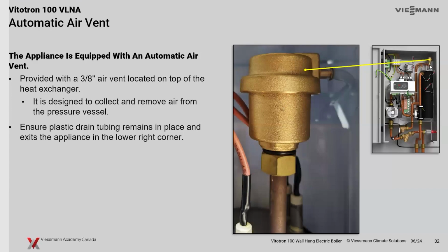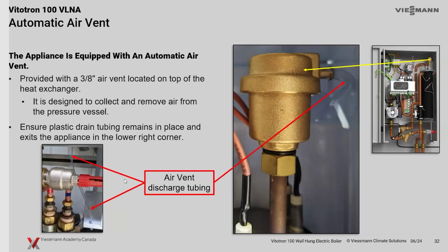There's an air vent at the very top of our heat exchanger here with the built-in elements. And of course, that is right at the top to make it easy to get the air out of our heat exchanger. It does have a little PVC pipe. You see a little bit of tubing connected here. The idea is that it goes down and hangs off the bottom here so that any water coming off this is not going to drip down on the machine. So we make sure that that's connected here. And we could take that down to the bottom here, and it kind of sits there. And should we have any issues, it'll just drip out here versus the interior of the unit itself.